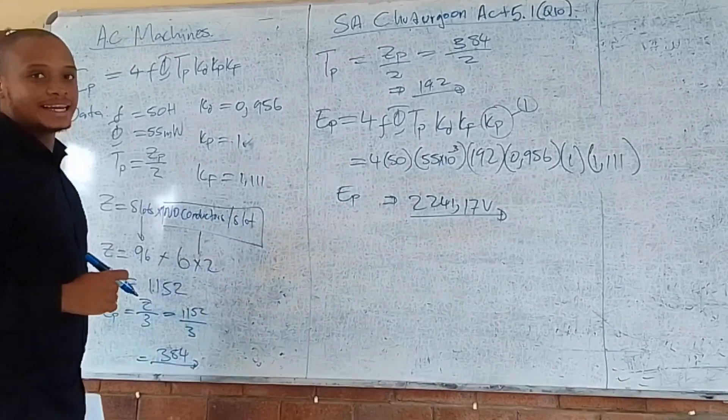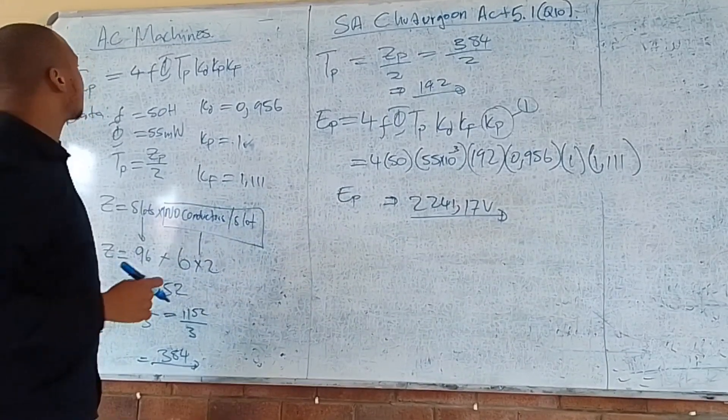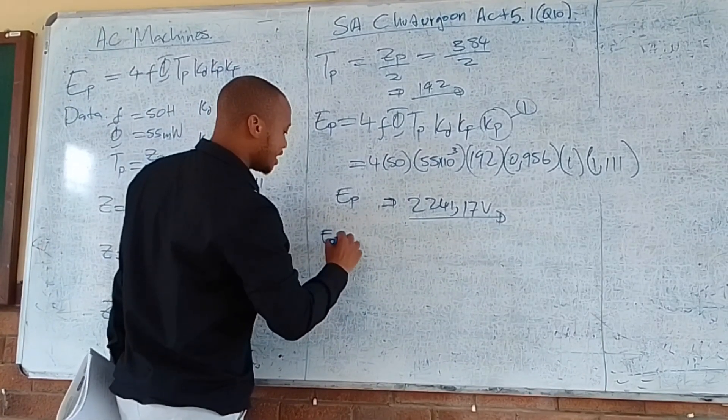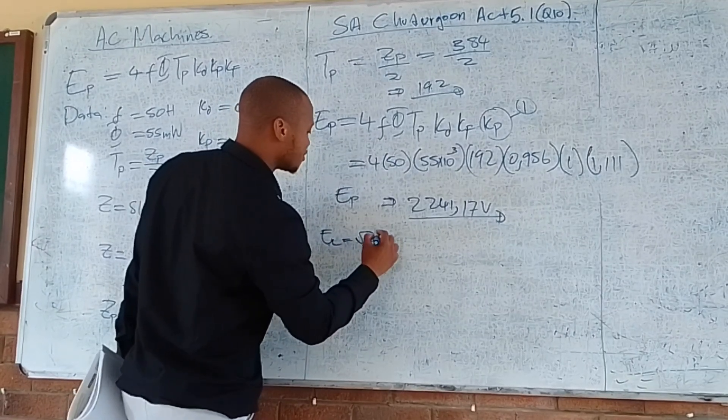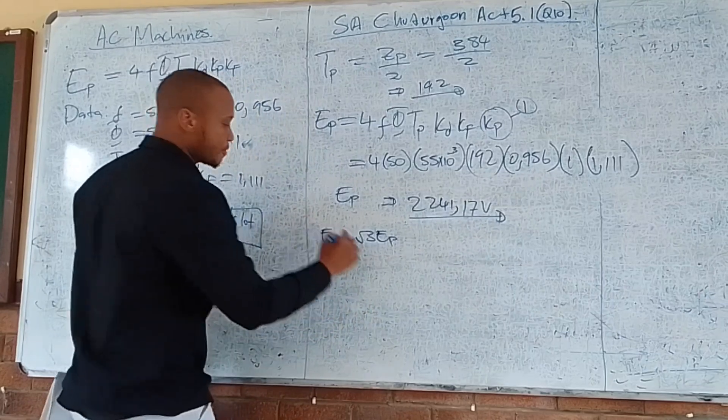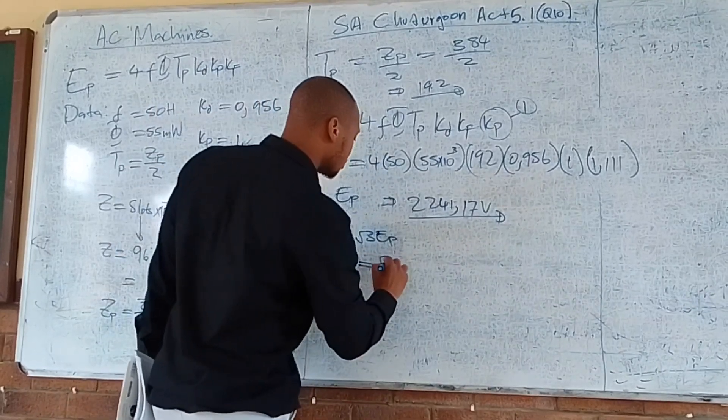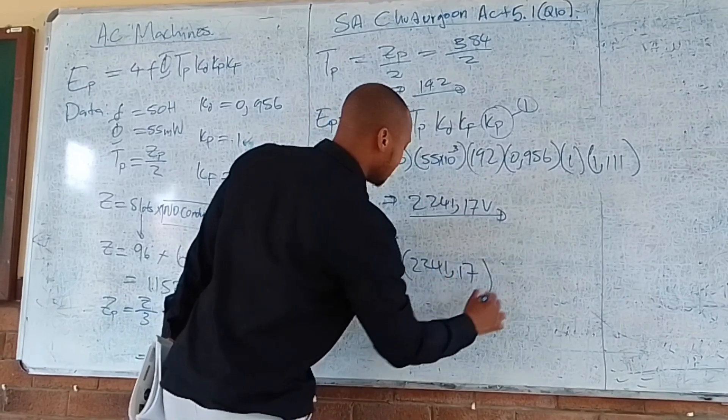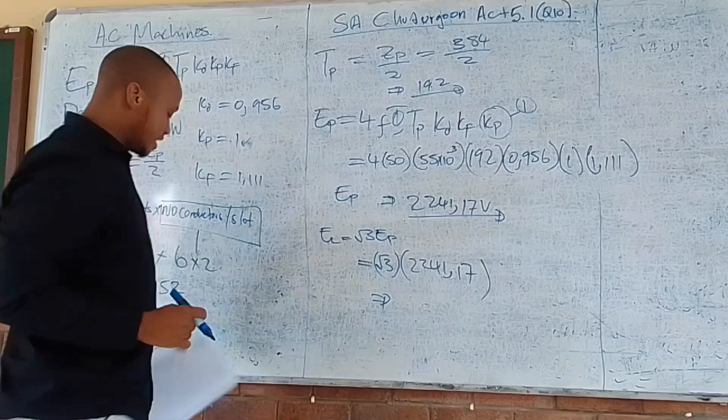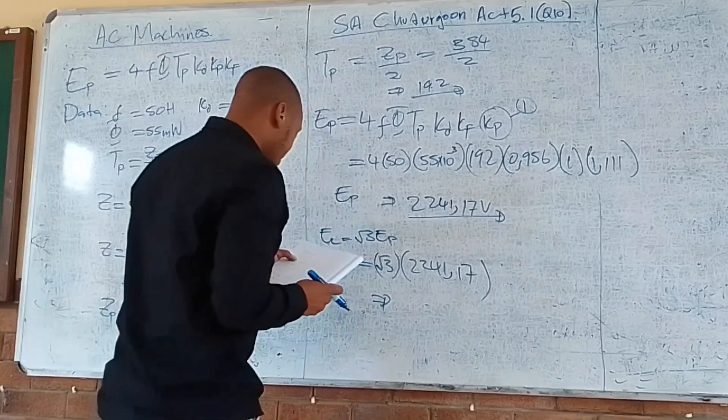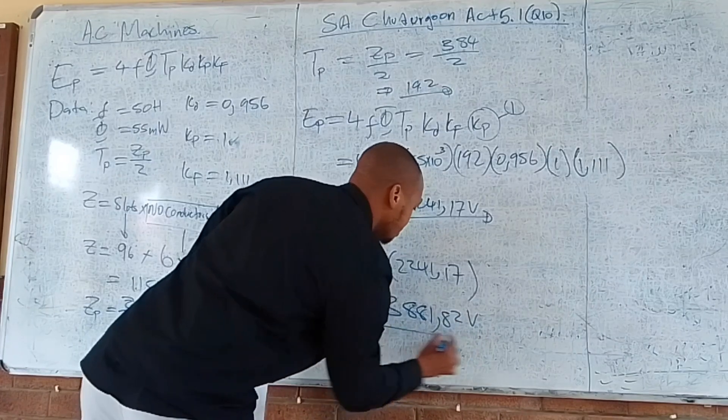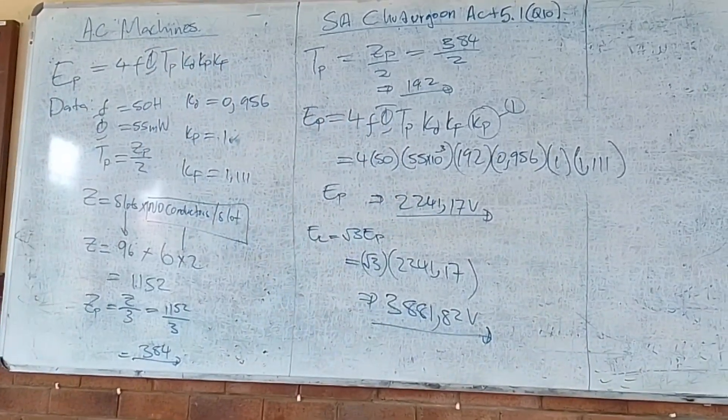The question wants you to calculate the line voltage. It's a star-connected machine, and you know that E line equals square root 3 times E phase. This means square root 3 multiplied by 2,241.17. When you calculate that, you should get 3,881.82 volts. That's the line voltage.